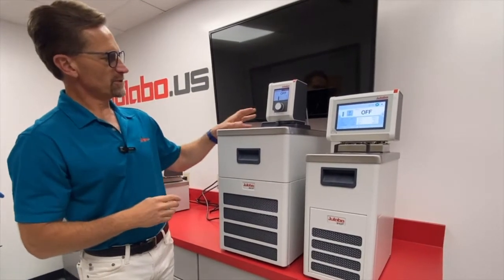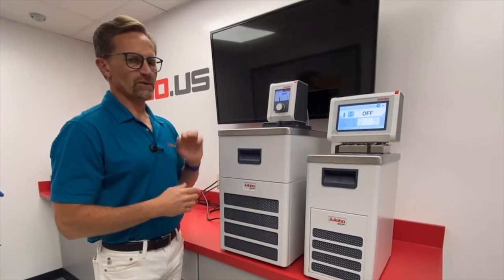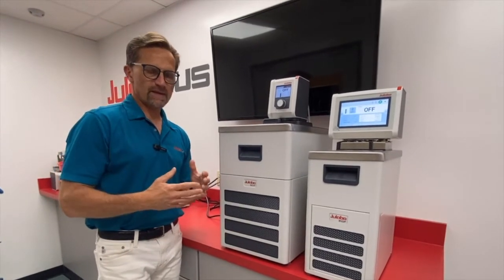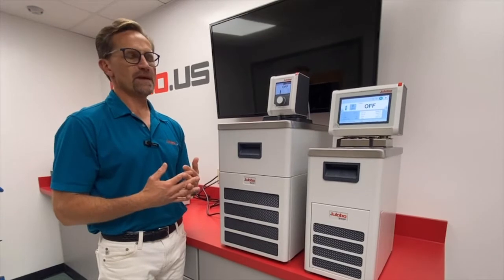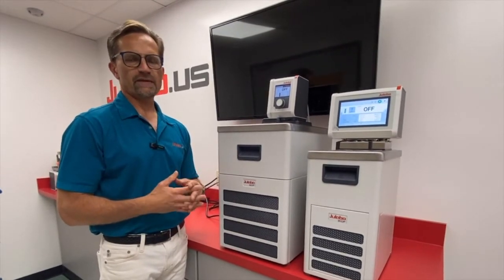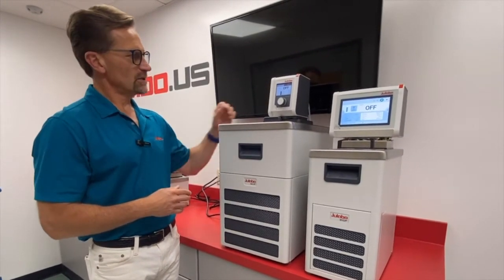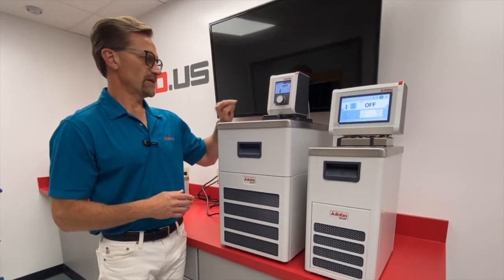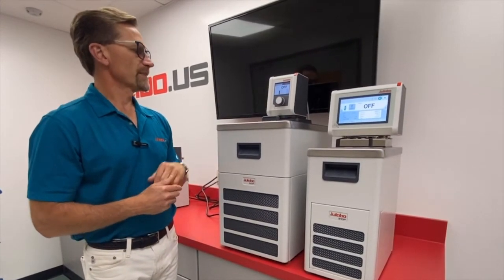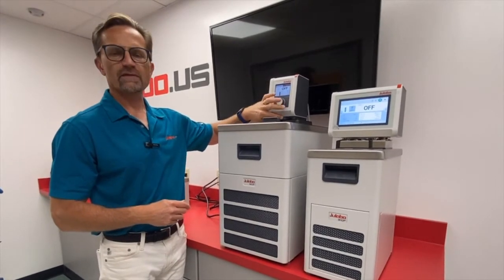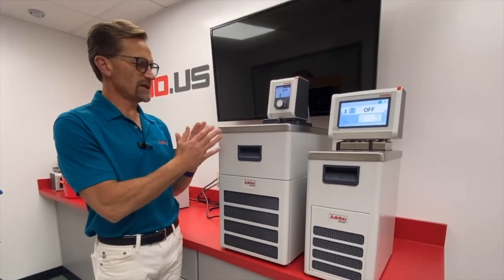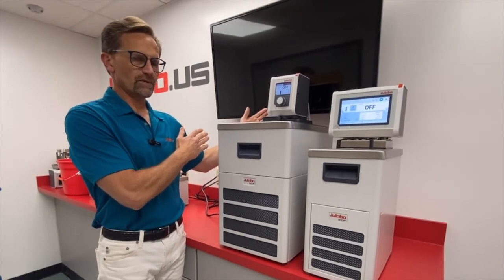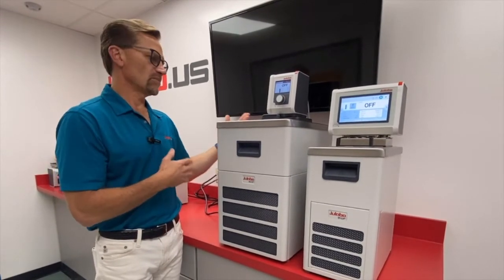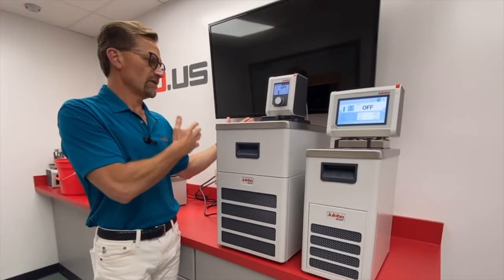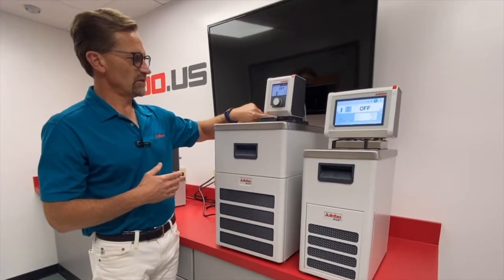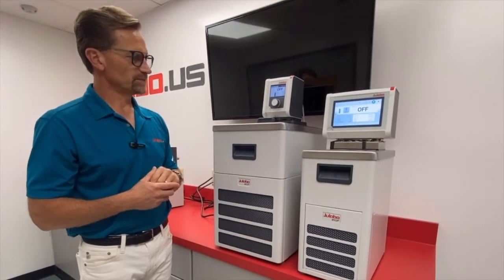Okay. From a pump perspective, the DYNEO has a pressure-only pump with flow rate capability of 8 to 27 liters per minute and a pressure of 1.5 to 10.2 psi. So you can adjust the pump speed with the menu here using the dial and click function. It also incorporates a manual diverter valve where you can physically adjust the ratio between the internal and external flow. For example, if you have the unit plumbed to an external application, you want to divert all of the flow over to that, you can move this over to the far left for 100% external.